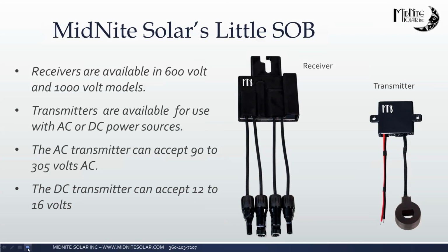industry do have a 24-volt power source located right there within the inverter. The nice thing about these is they are designed to fit with the transmitter within the inverter casing. It's a very small item, and so that allows it to be concealed and keep your installation looking nice and tidy. Yeah, and to expand on that, in a grid-tied inverter, in that scenario that Sue just mentioned, if the transmitter is in the wiring compartment, you can wire it to the 240 volts in the grid-tie inverter. So then utility failure does trigger a rapid shutdown. So it becomes very elegant.